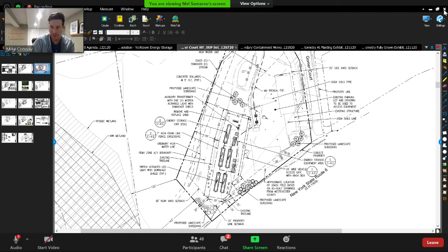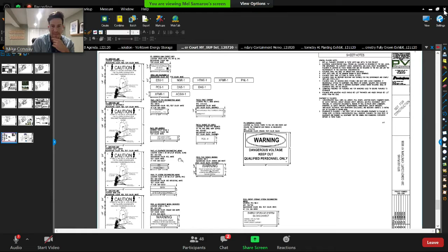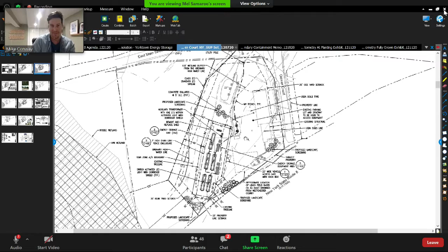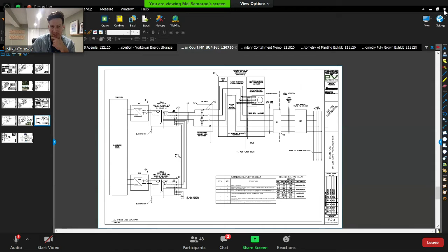The transformers will be customer owned, not owned by Con Ed, so they won't necessarily have the exact same nomenclature that Con Ed would use, though they will include the same warnings and labels pursuant to NFPA and the National Electric Code. They'll have arc flash labels informing what type of personal protective equipment people need to wear to service the equipment, things like that. As for labeling on the drawing, I'm not sure if we have that specifically there, but on the layout I'm sure it's on the single line drawings included in the package that specifically call out the transformers.